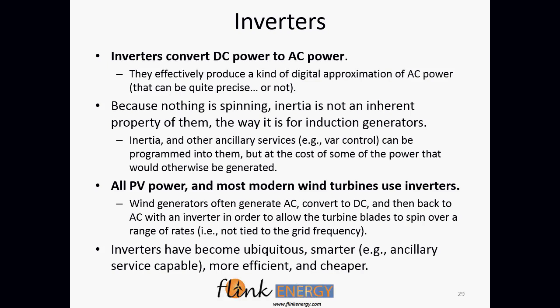All photovoltaics use inverters, but the other thing is most wind turbines do as well. I don't know how many of you remember in the 80s, Bonneville had these big wind turbines up near Goldendale, right? Yep. And they kept breaking down. What would break down on them, as I understood it, was the shaft between the turbine blades and the generator. A big gust of wind would come up, and the turbine blades would want to spin faster. But they were synchronous devices, meaning they were in lockstep with every other generator in the power grid. So that wind and those turbine blades were really trying to spin up the entire grid. And that's not happening. So instead, the crankshaft broke routinely.